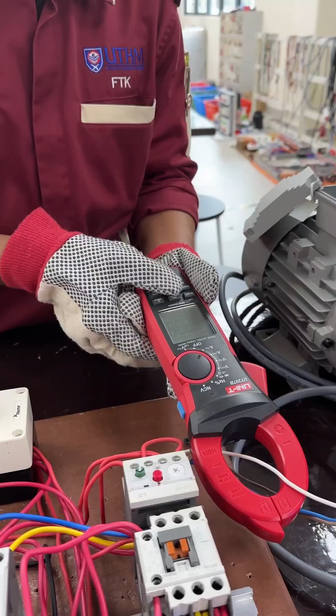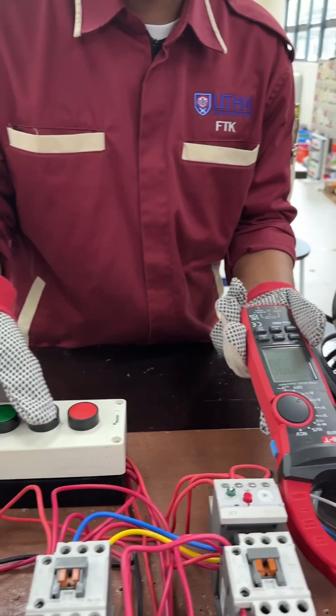First of all, we must stop the motor. Then we take any of the voltage lines. As you can see, it's off, then turn on, 0, inrush. We want to check the inrush current first, so we must push the start button, with forward or reverse selected, so I try with forward. As you can see, 0 ampere, so the inrush current is 8.25.